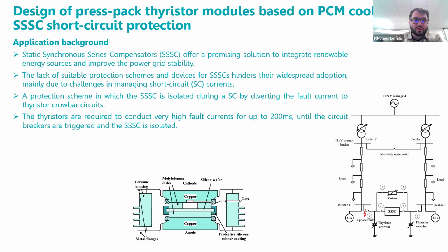So when you have a series static compensator, and then you have a fault along the grid lines, because these compensators normally work with IGBT modules and they cannot handle exceedingly high currents, one way to protect them is to divert the current into thyristor modules. We're using thyristor crowbar circuits. These thyristors have to conduct the current until the circuit breakers are triggered, and then the static compensator is isolated.